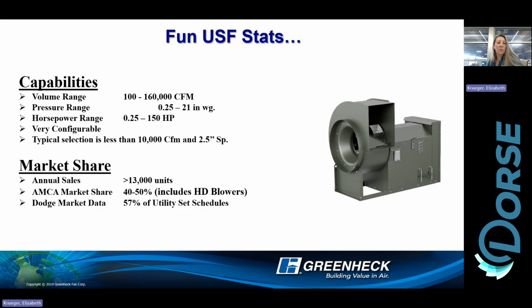Basically, here's what the USF can do. It can move a little air or a lot of air. They're really good at building pressure, up to 21 inches of static pressure. We can put 150 horsepower motors on these if we need to, but generally we'll see a half horse to 7.5 horse range as more typical. These fans are highly configurable.